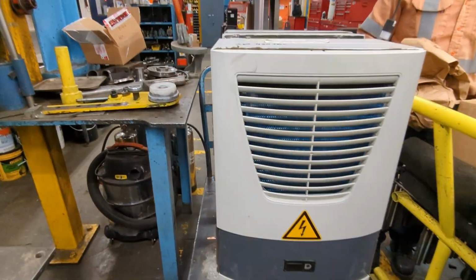That's where we checked out two little electrical closet air conditioners. Basically throughout the floor, they've got these electrical cabinets, pretty big, that generate a lot of heat. So they've got this little air conditioner unit attached to the thing to keep that cabinet cold, and periodically these things just stop working. Sometimes we get to work in the plant, in the factory where the electrical closet is, but sometimes they'll bring the units out to the maintenance workshop, and then we get to work on them out in the open, which is a lot easier to test and work on.